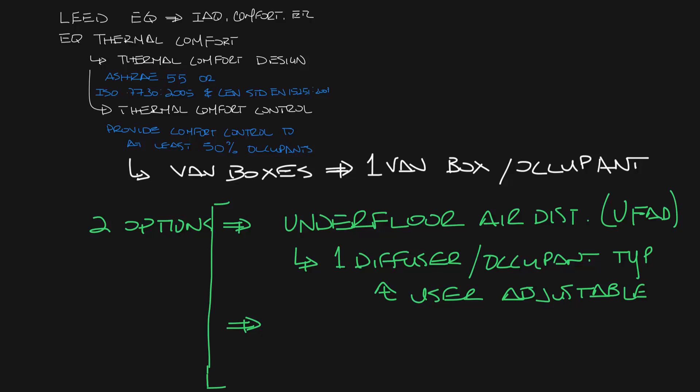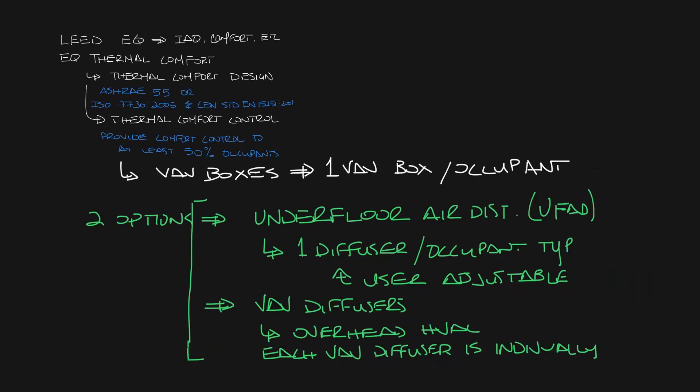Another option is to use VAV diffusers. This allows you to do a typical overhead HVAC system, but instead of VAV boxes serving several zones, you would use VAV diffusers. And then each VAV diffuser is individually adjustable, so you can give 50% of your occupants Thermal Comfort Control.